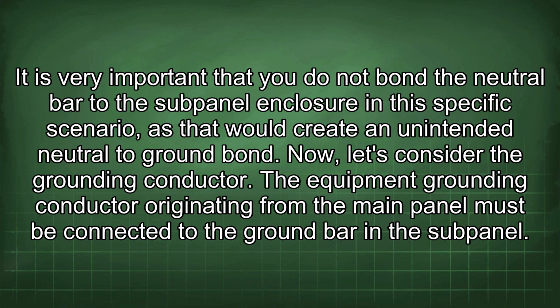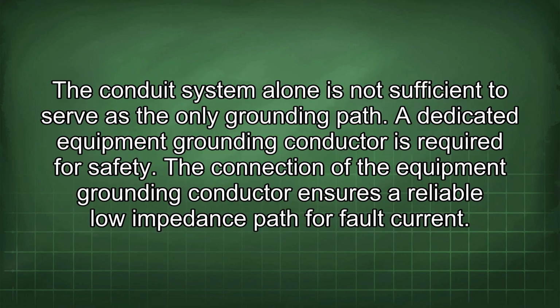Now let's consider the grounding conductor. The equipment grounding conductor originating from the main panel must be connected to the ground bar in the subpanel. The conduit system alone is not sufficient to serve as the only grounding path. A dedicated equipment grounding conductor is required for safety. The connection of the equipment grounding conductor ensures a reliable low impedance path for fault current.